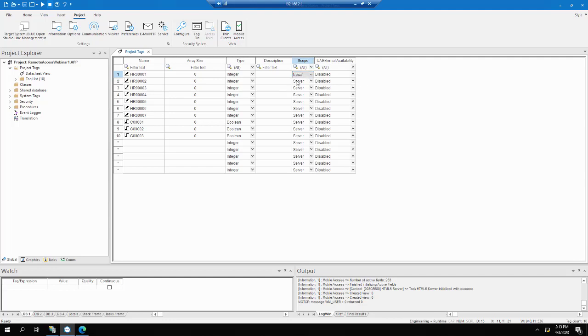Okay? Now, I do have the ability to say local, and what that means is that in each viewer place or in the runtime, I have a local copy of this data, and also in the client, I will have my own local data that is completely separate. And notice that if this is local, this will not actually go to the PLC, but it uses this holding register index number to figure out that's just the objects that have everything tied to that. The clients will have their own local copy of that data. Okay, so to illustrate that, I'm going to make that local.